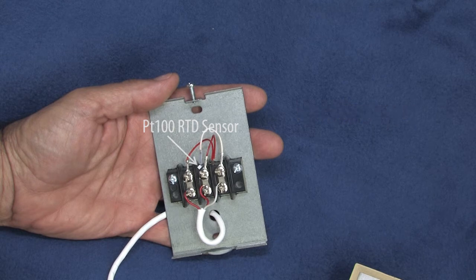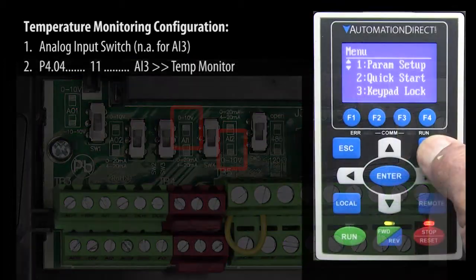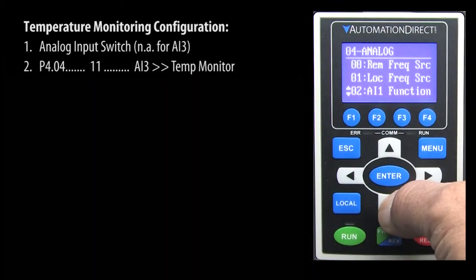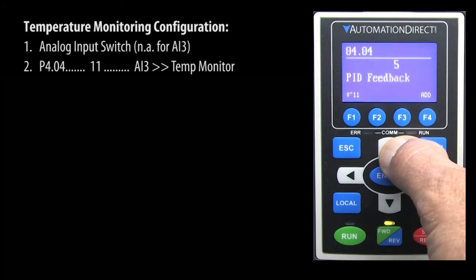Great, we're wired up so let's configure the drive. Analog input 3 only reads voltages so there's no switch to flip. If we were using analog input 1 or 2, we would need to make sure that the switch on the terminal board is set to the 0 to 10 volt position. In parameter 404, we tell the drive to use analog input 3 as the temperature monitor by selecting 11.